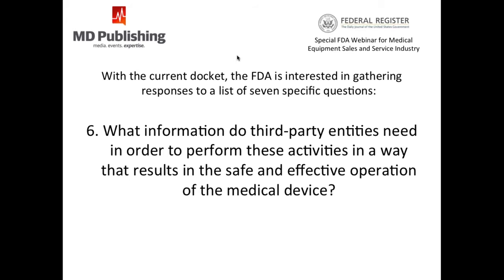You have a design validation, design verification and validation process, but the service maintenance procedure is not required to be validated. So right now we sometimes have recommendations by manufacturers that when you start reading, you say, well, this isn't even possible to do.